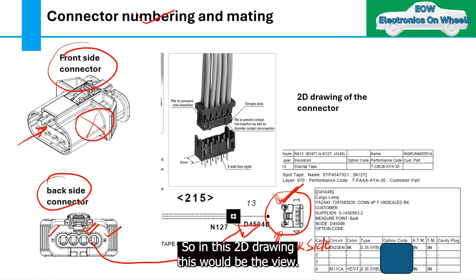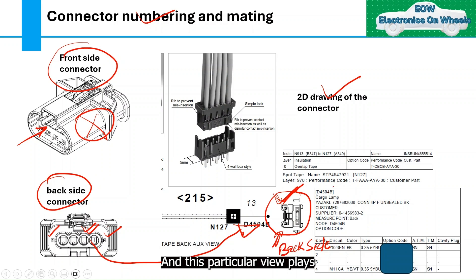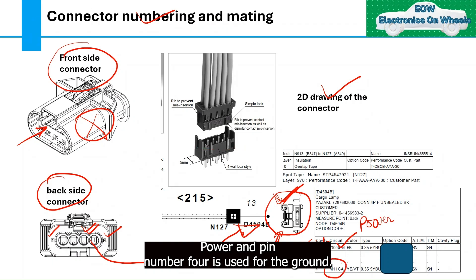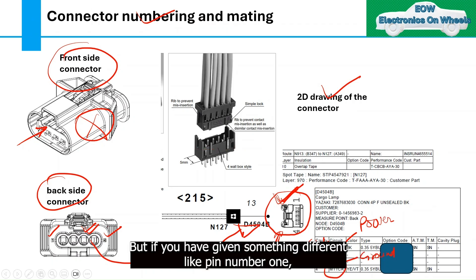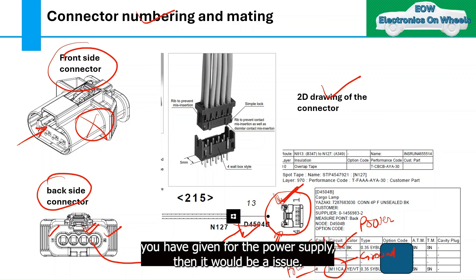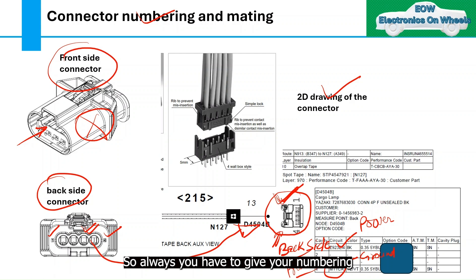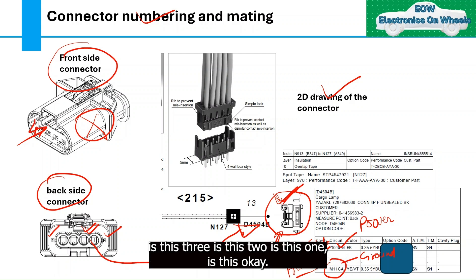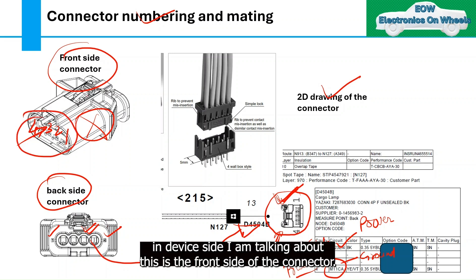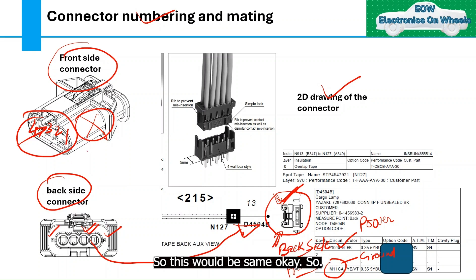So in the 2D drawing, the back side view is the one placed — this is very critical when assigning signals. Suppose pin number 1 is for power supply and pin number 4 is for ground. If you assign them incorrectly — pin 1 for ground and pin 4 for power — it would cause an issue. You must always give numbering based on the mating (device) side.